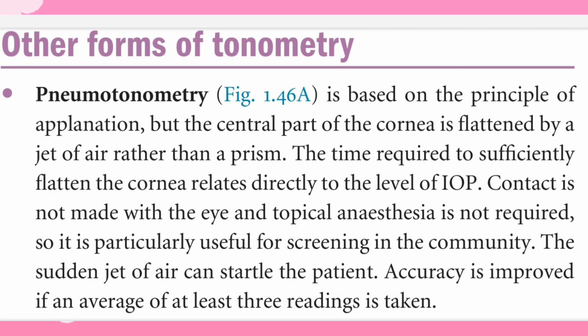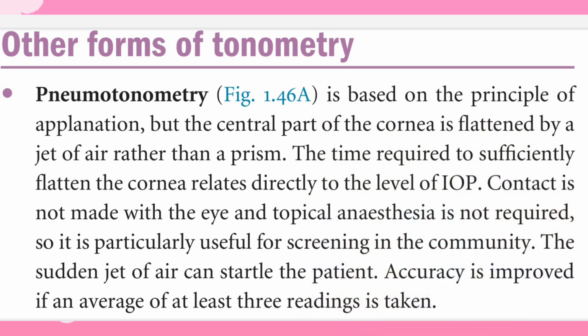Other forms of tonometry. Pneumotonometry, figure 1.46a, is based on the principle of applanation, but the central part of the cornea is flattened by a jet of air rather than a prism. The time required to sufficiently flatten the cornea relates directly to the level of IOP. Contact is not made with the eye and topical anesthesia is not required, so it is particularly useful for screening in the community. The sudden jet of air can startle the patient. Accuracy is improved if an average of at least 3 readings is taken.